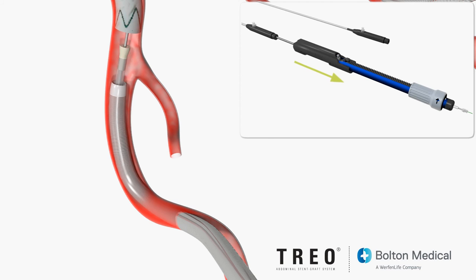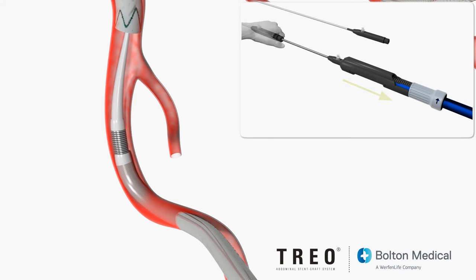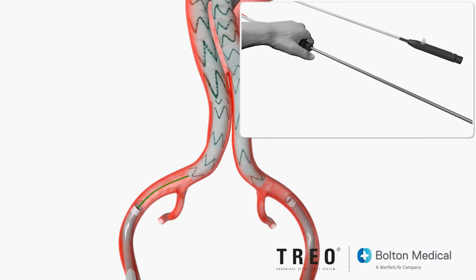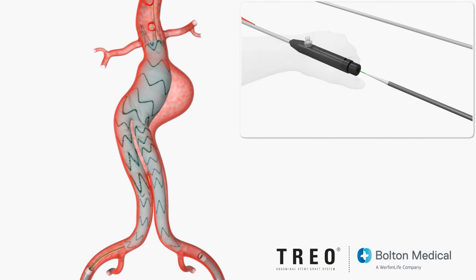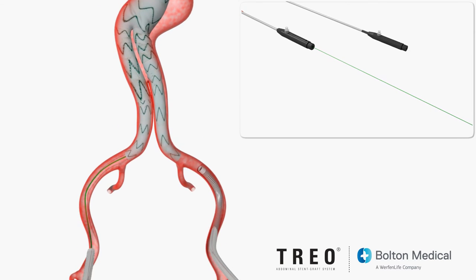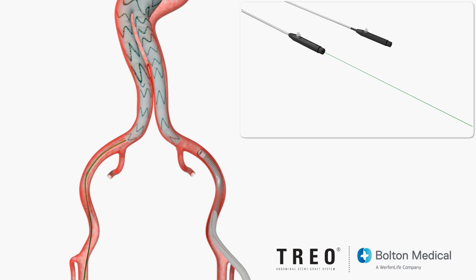The ipsilateral leg extension delivery system can now be removed from the main system sheath. It is not necessary to reseat the tip of the ipsilateral leg extension delivery system when it is used in conjunction with the main delivery system sheath. Accessory devices may now be used with the sheath of the main delivery system. If desired, the leg extension delivery system on the contralateral side may be disassembled in the same manner as the main delivery system in order to provide a sheath for the use of compatible accessory devices.